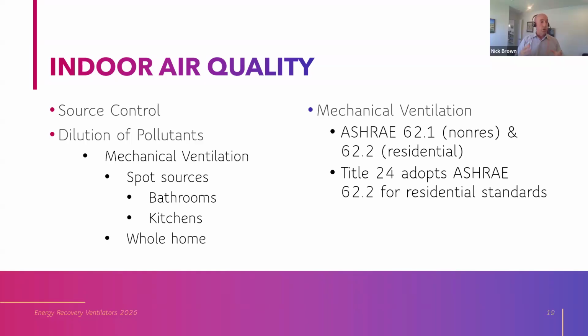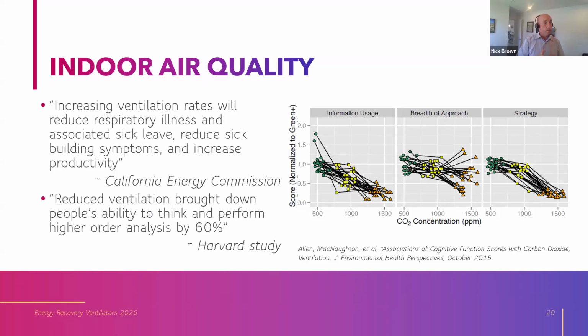The code requires spot exhaust ventilation in bathrooms and kitchens, that's your kitchen range vent hood, and it requires whole home IAQ fan ventilation. ASHRAE 62.1 covers whole building ventilation requirements for non-residential buildings, and 62.2 covers residential. That ASHRAE standard is the basis, and Title 24 has adopted 62.2 for residential building types. Why? Because increasing ventilation rates will reduce respiratory illness and associated sick leave, reduce sick building symptoms, and increase productivity. That was the CEC's quote when they adopted a newer version of 62.2.